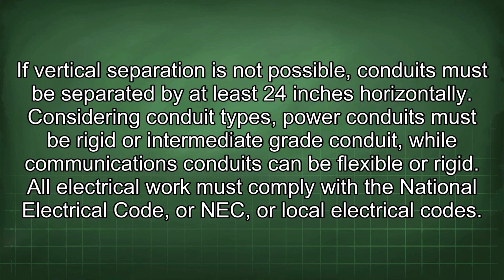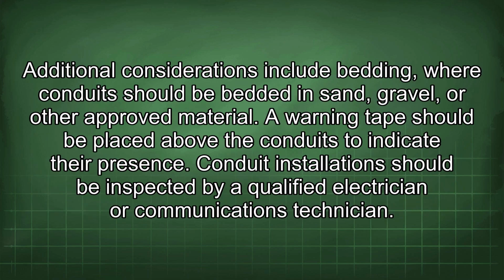Considering conduit types, power conduits must be rigid or intermediate grade conduit, while communications conduits can be flexible or rigid. All electrical work must comply with the National Electrical Code, or NEC, or local electrical codes. Additional considerations include bedding, where conduits should be bedded in sand, gravel, or other approved material. A warning tape should be placed above the conduits to indicate their presence.